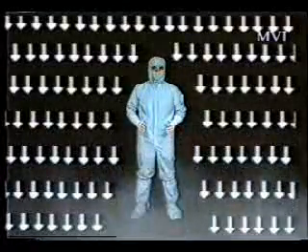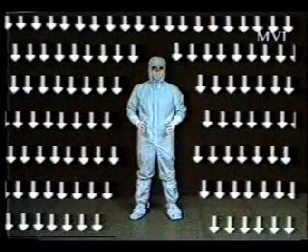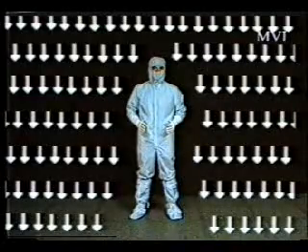It's the human microenvironment which causes skin flakes shed by the body to be dispersed by the effect of heat and pressure radiating them into the atmosphere. In a cleanroom, the body increases the divergence of downward vertical laminar airflow and may be considered to form a symmetrical bell shape, which is intended to control the effects of the inverted bell-shaped air current created by the human microenvironment. Whilst a person is stationary, the two forces are dominated by the downward airflow of the cleanroom, and particles dispersed are carried away by the rapid air changes.